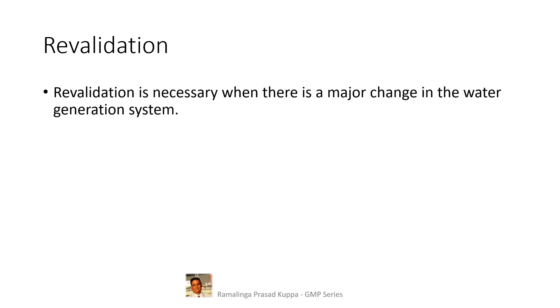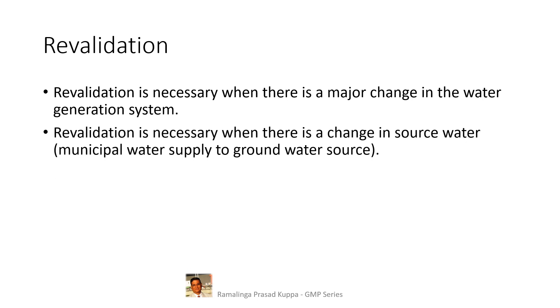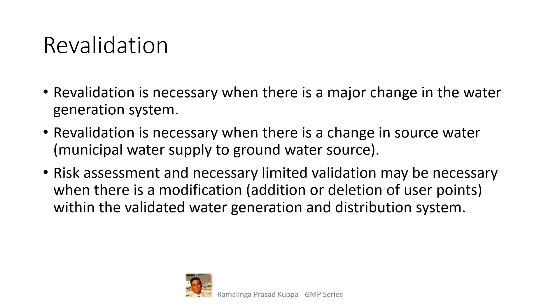Let us see the conditions for revalidation of water generation and distribution systems. Revalidation is necessary when there is a major change in the water generation and distribution system — this is a general rule — to establish that any change has no adverse impact on the validated status of the system. As discussed earlier, the source water has significant impact on the validated status of the water system. Risk assessment and necessary limited validation may be necessary when there is a modification, addition, or deletion of user points within the validated water generation and distribution system.